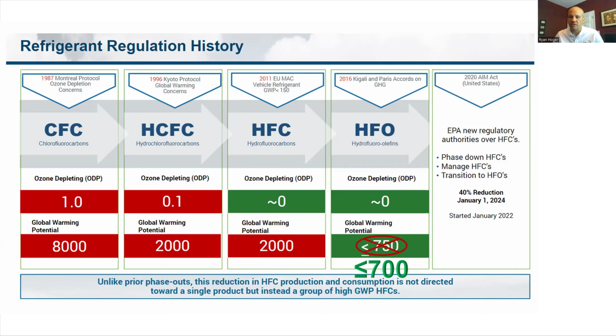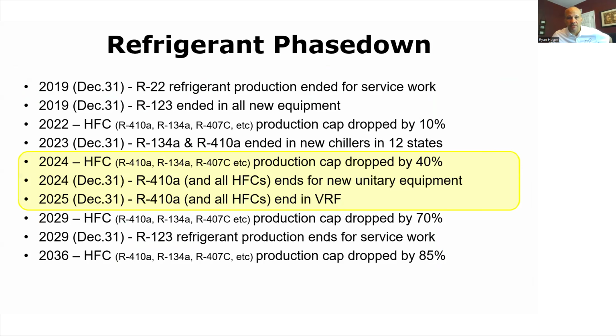It was supposed to be, what was it? 550, no, 500, then 650, then 750, then they finally settled on 700. I don't know why they keep changing their mind. It's weird. There's not even any refrigerants that exist between 700 and 750 that I can find. So I don't even know why they changed it. But that's the kind of stuff that your government does. So we got to get all the refrigerants down below 700. We already got the ozone depleting potential down to zero for these refrigerants. So this is the next phase in that process.